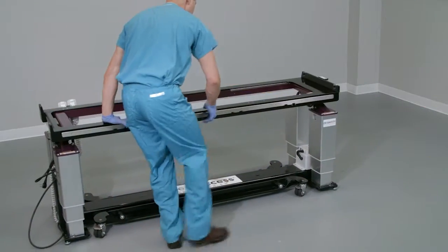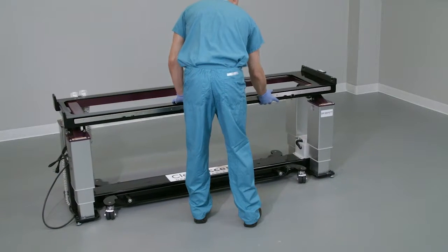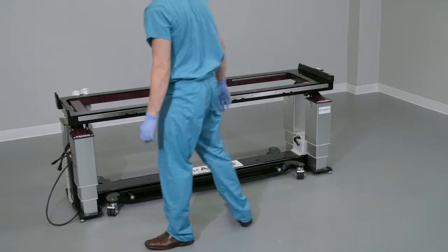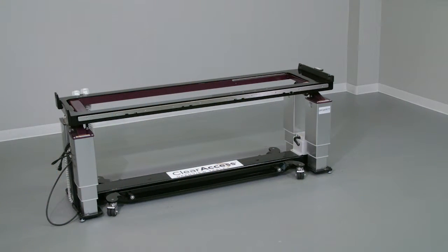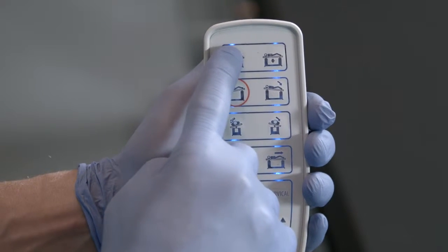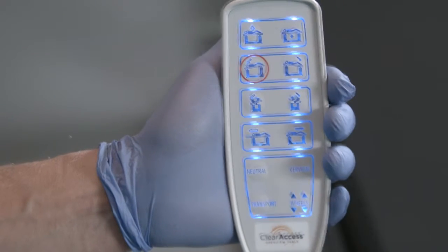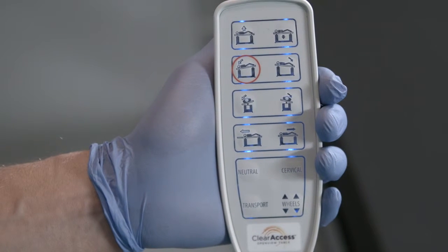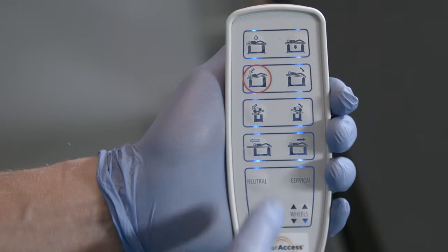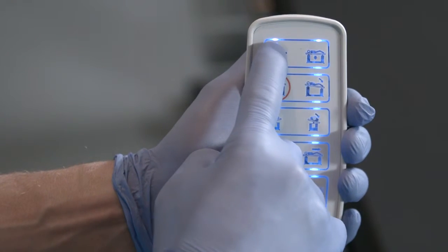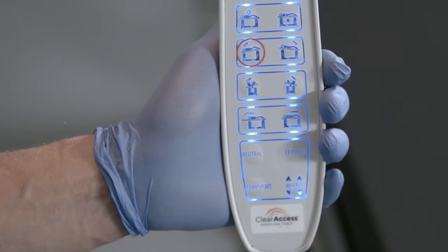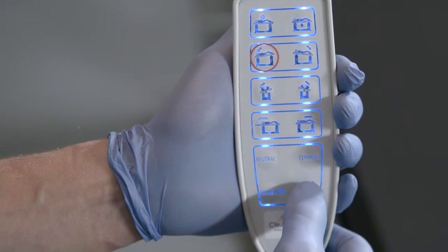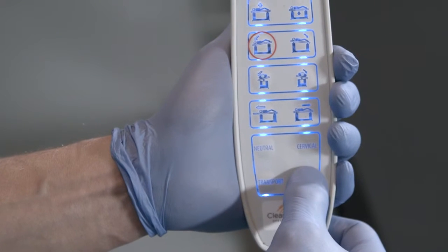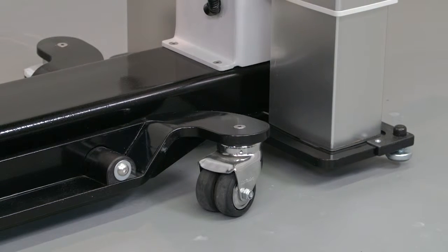Move the Clear Access table to the preferred location in the OR. To lock the table to the floor, press any button on the hand controller to wake it. Both hand controllers will auto-sleep if inactive for 30 seconds. Press any button to reactivate, and then lock the table by pressing the wheels button firmly once and releasing. You'll note an audible beep as the table is lowered to the ground, warning caregivers to keep personnel and equipment clear of the table.